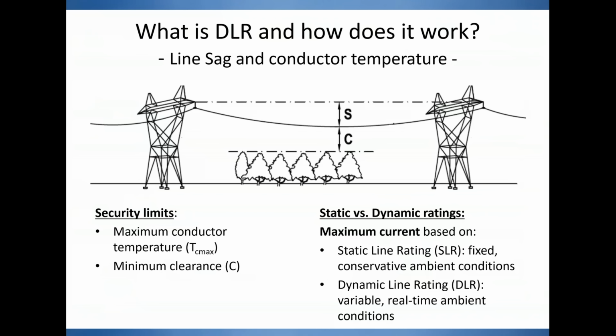So DLR is a technology that tries to deliver more capacity of existing lines, and I'm talking here specifically of overhead lines. The next presentation will talk about underground cables where similar concepts can apply. So an overhead line typically is limited in its thermal capacity by the maximum operating temperature of the conductor, or by the maximum sag, which is determined by the minimum distance to the ground, so that a fault isn't created between the line and the obstacle on the ground.